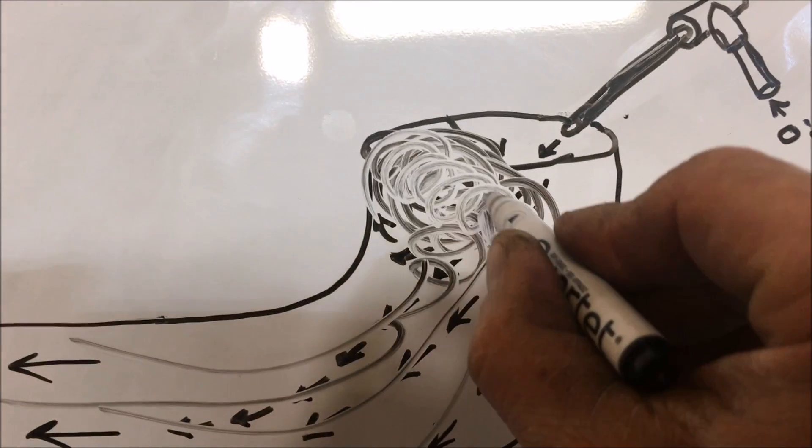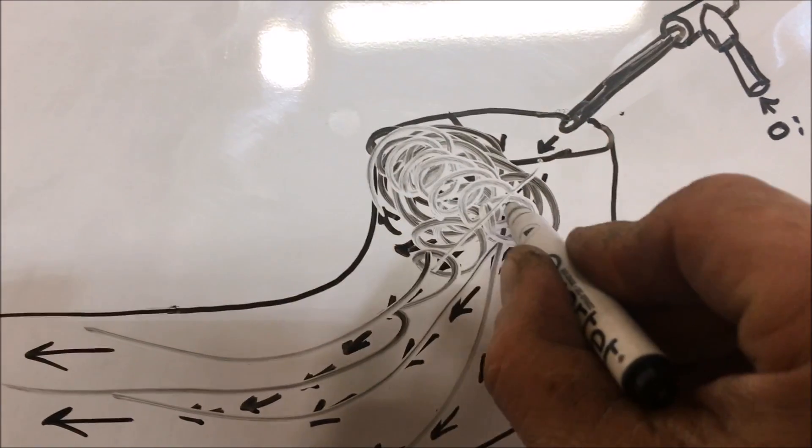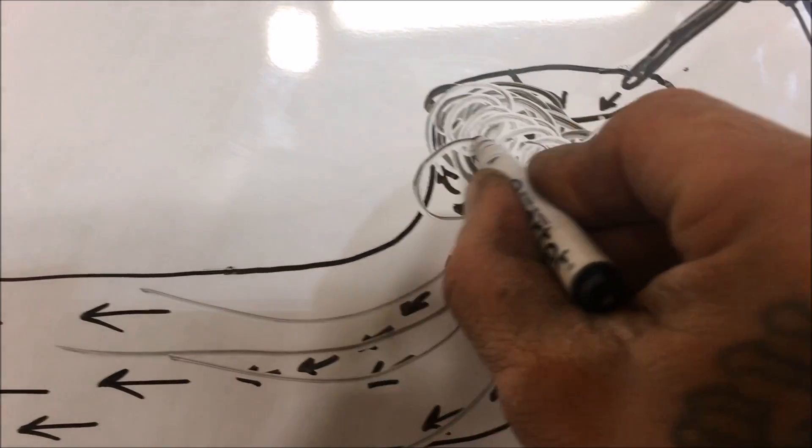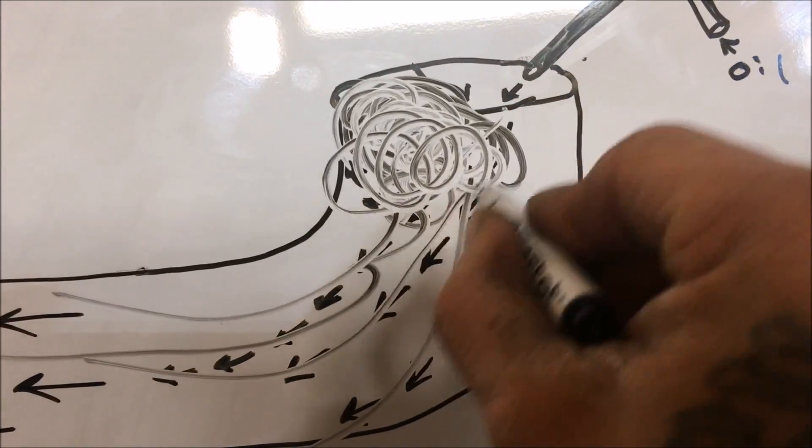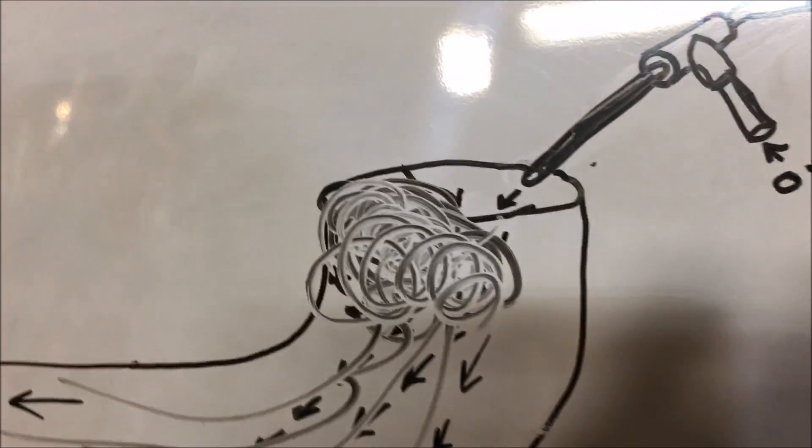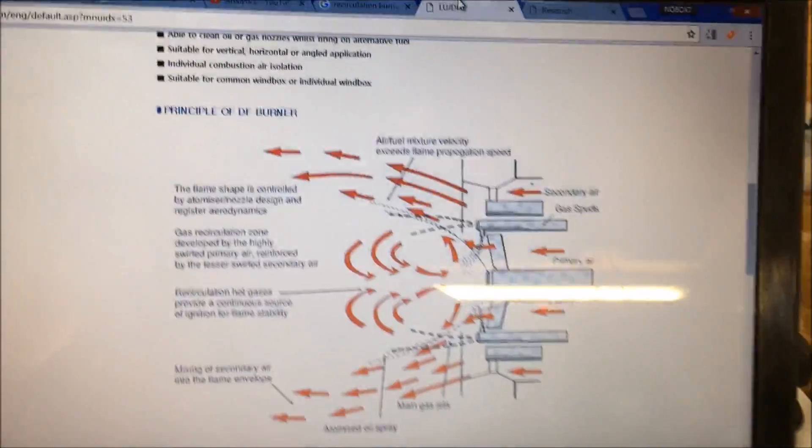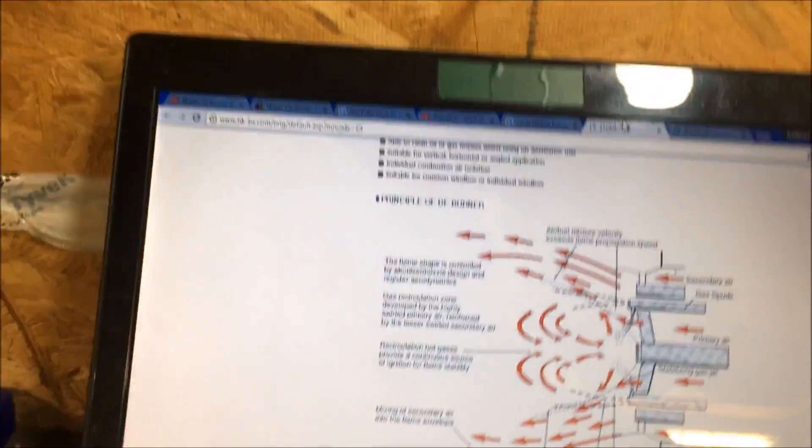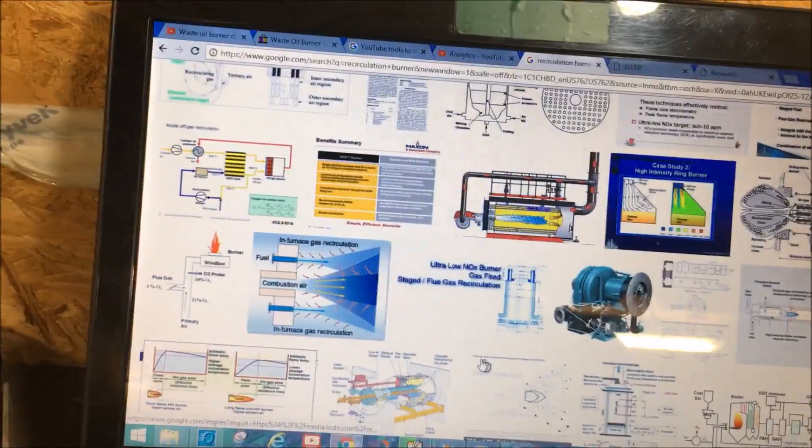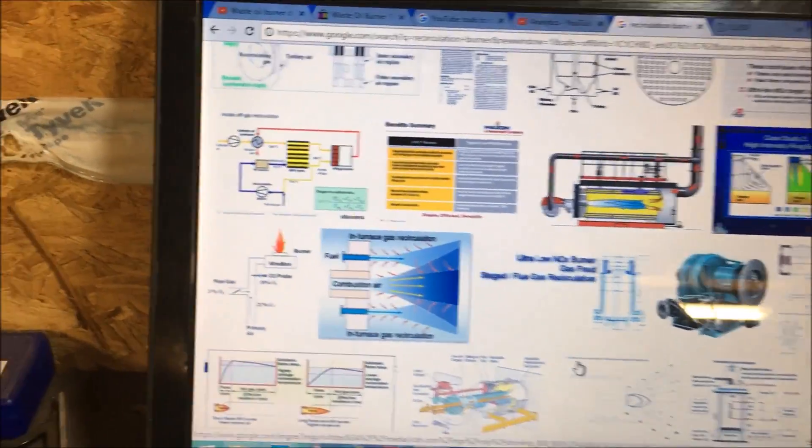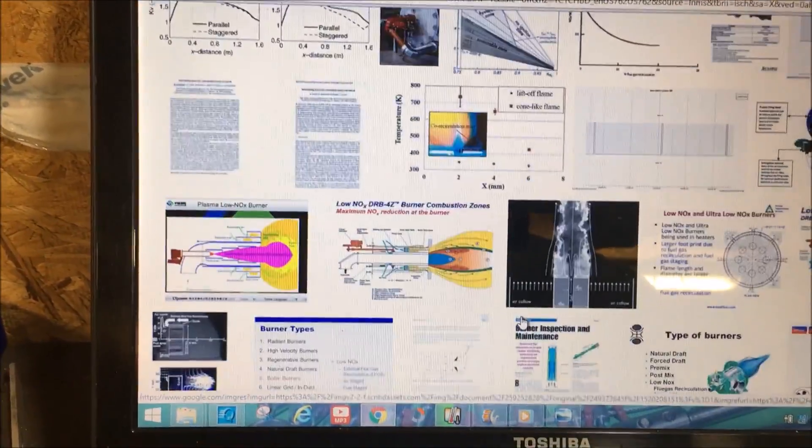This is a geometrically induced flame holder. It's causing an eddy current inside this burner. It swirls in this direction - the air comes in, hits molecules in this region, and causes them to swirl. That's what happens right there, and that is a recirculation effect that is sought after in many applications.